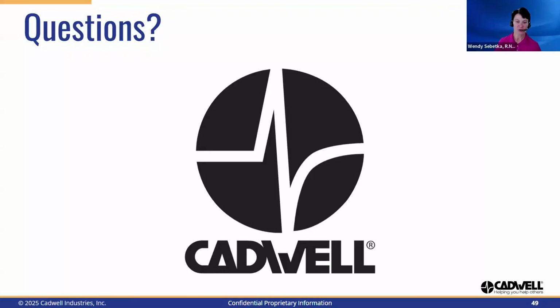So the question is, what do I do if the customer doesn't have proper grounding? If the machine is not properly grounded, I would suggest adding one. If we're talking about environmental grounding, my recommendation would be to contact an electrical contractor who could come in and install an electrical ground for you. The earth ground is something that can be added later. So my recommendation would be to see if your electrical team would be able to install that ground.